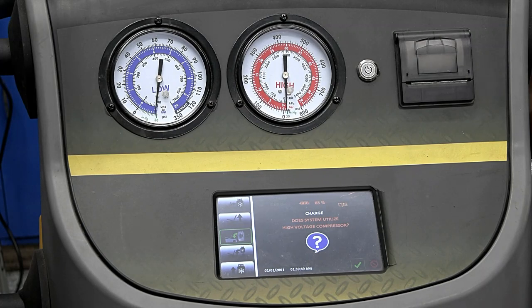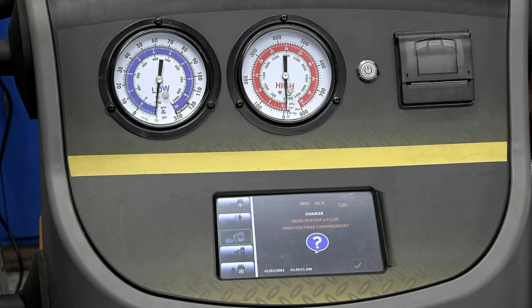Does the system utilize a high voltage compressor? The reason why they're asking that, if it's a hybrid or EV, first of all, no PAG oil goes in there, because PAG is an alkaline and you could get an isolation fault.